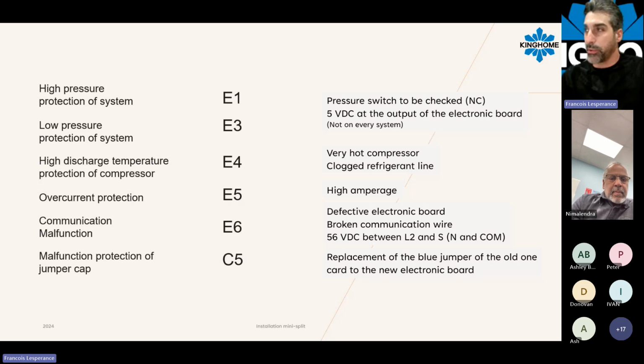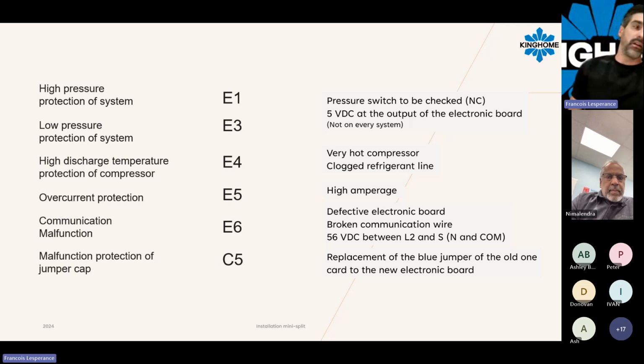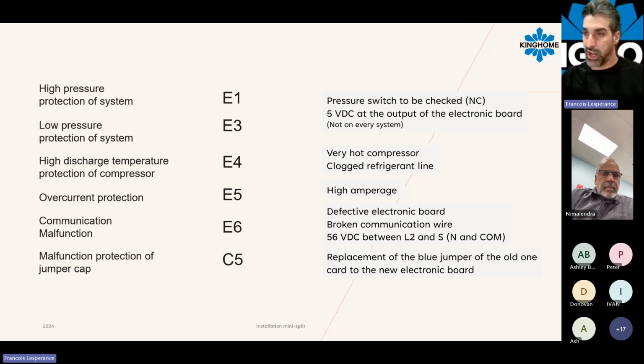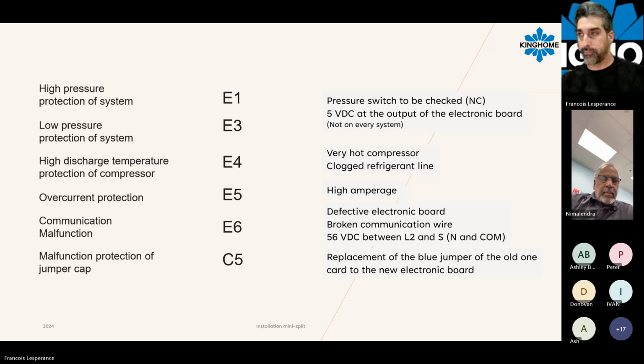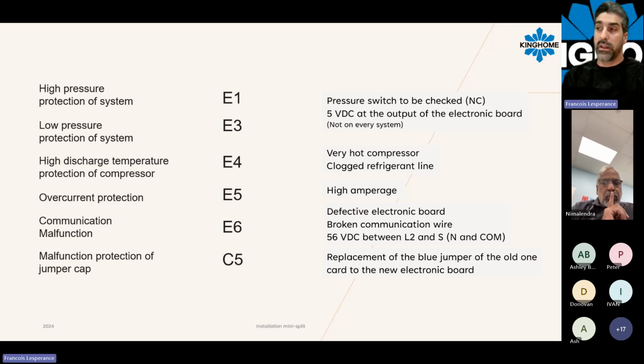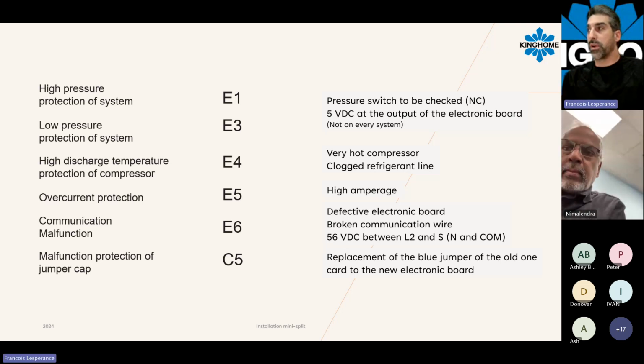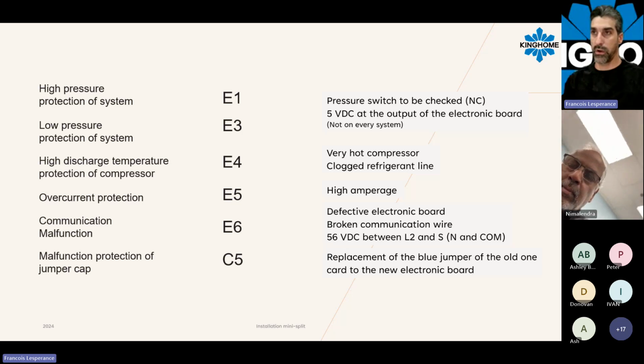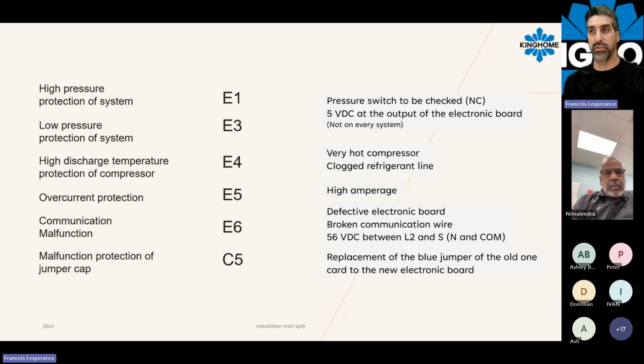Looking at the error codes, Kinghome is always using the same kind of error codes, whether it's for a central unit or for ductless. E1 and E3 are related to the pressure switch. E1 is high pressure switch protection. E3 is low pressure switch protection.